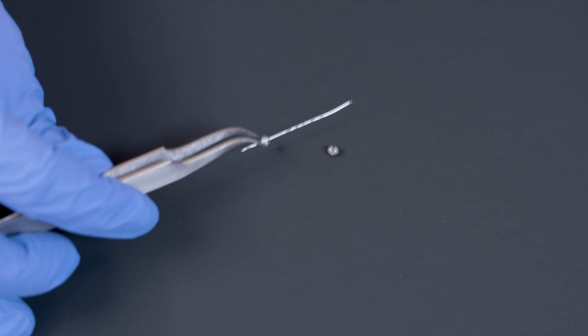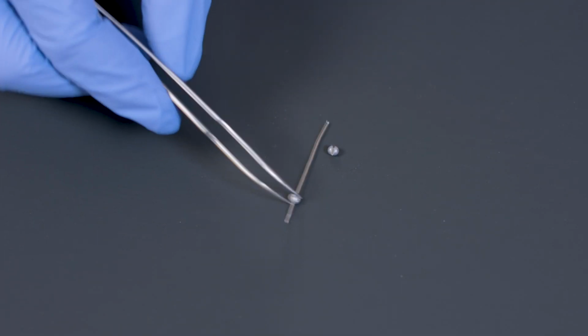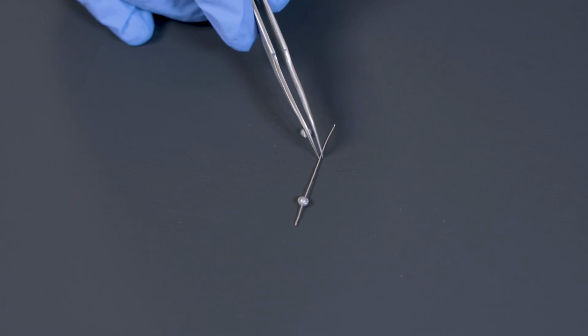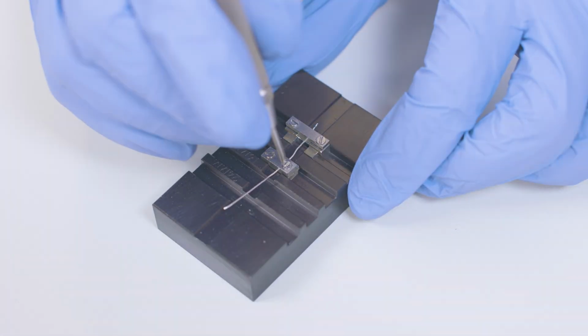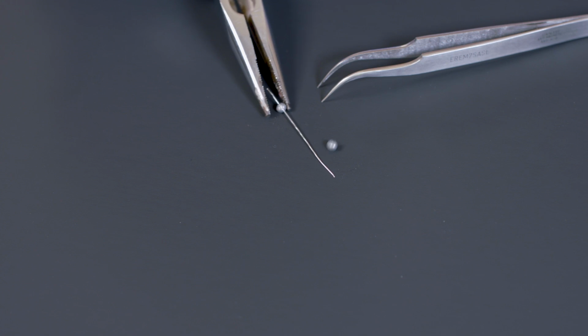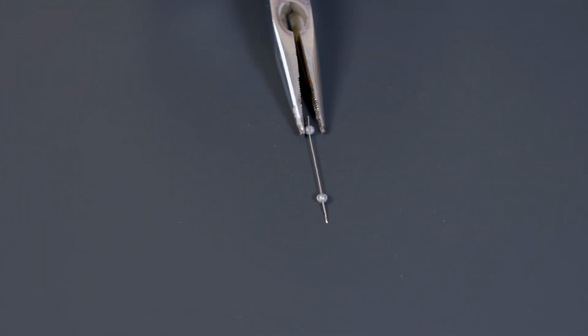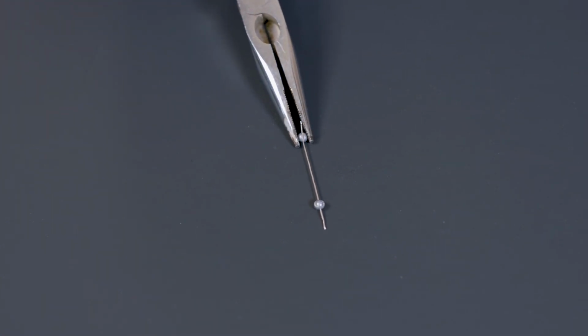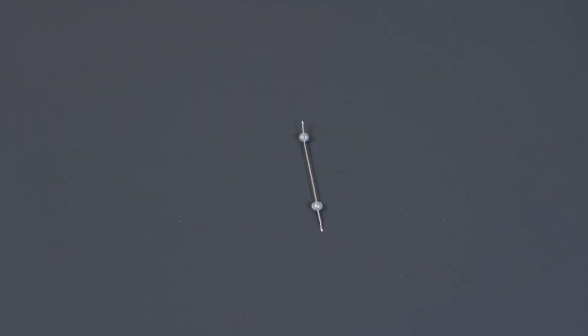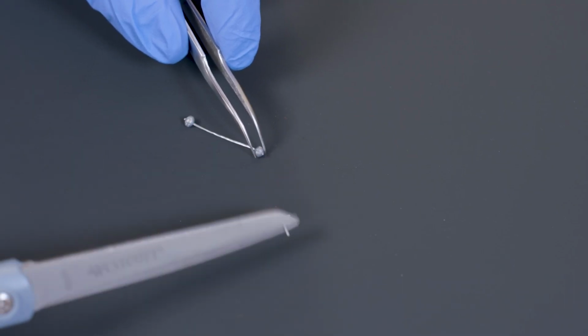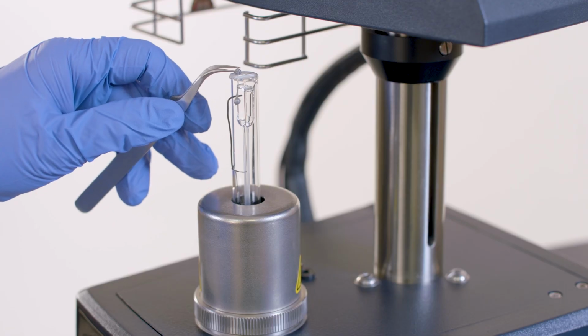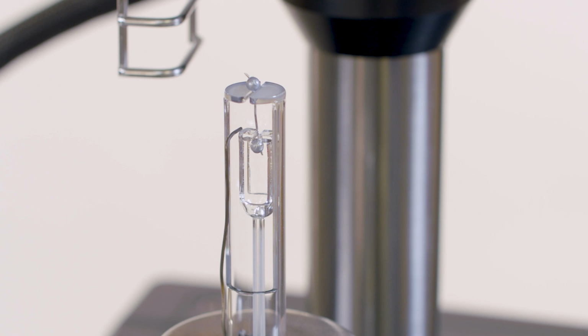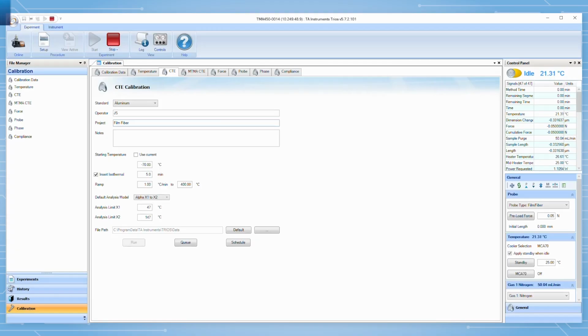For the temperature calibration, you will prepare an indium wire. This can be accomplished using cleaved aluminum balls or the included film clamp. The metal wire is crimped into cleaved aluminum balls. Indium wire is malleable. Clamp down with only enough force to grip tightly, but without breaking the wire. Trim the excess sample after crimping. The recorded melting point of this standard is compared to the known melting point, and the offset is applied for temperature calibration.